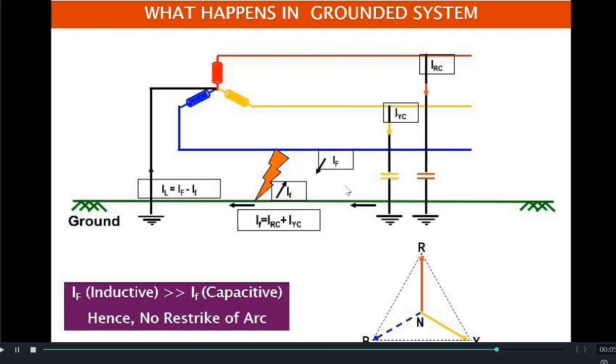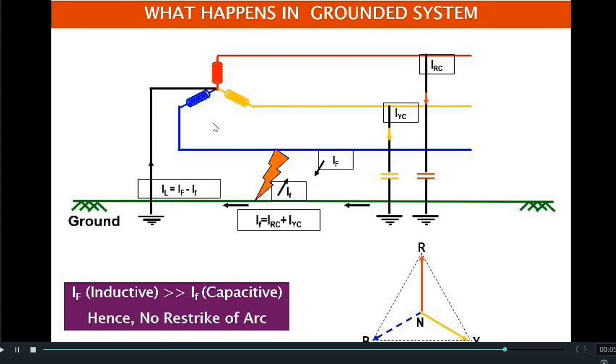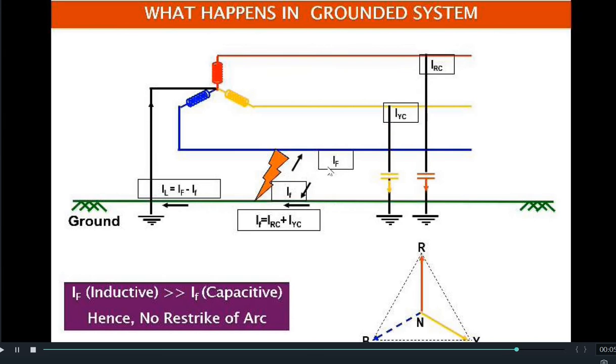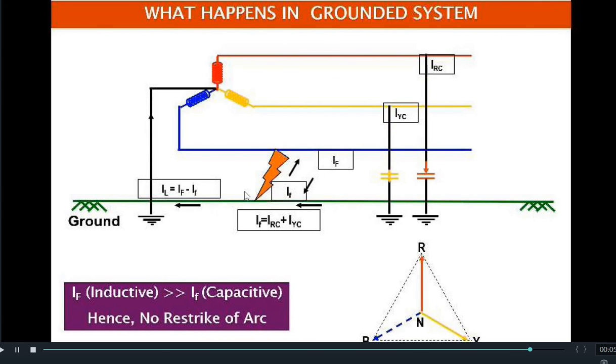There are two components of fault current: first, the capacitive current IRC plus IYC flowing through the faulty path; second, the inductive fault current due to the B phase fault, flowing from B phase through the faulty path to ground and then to neutral. This inductive fault current will be much higher than the capacitive current from R and Y phases, making it sufficient to distinguish the fault and isolate it from the system.